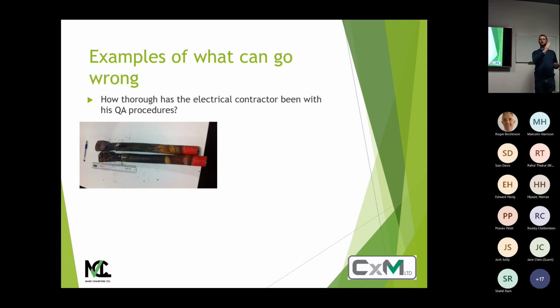The control system went, "Oh, I've lost my volts. I'll start my generators up." Start the generators up, switch over the generators, the cables would cool down, go back onto the bars, the volts will come back again. The generator control goes, "I've got my mains back. If that's okay there for another 10 minutes, I'll go back to mains." "Yep, go back to mains." Cables have then got load on them, they'd warm up, and they'd move again, and the process continued.